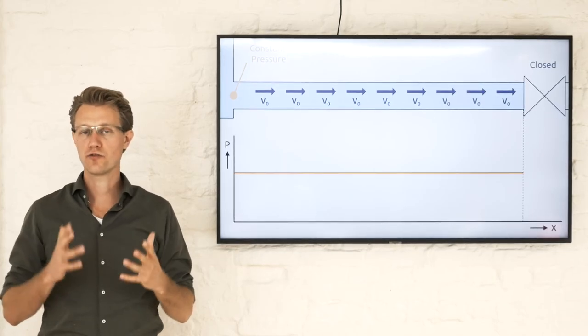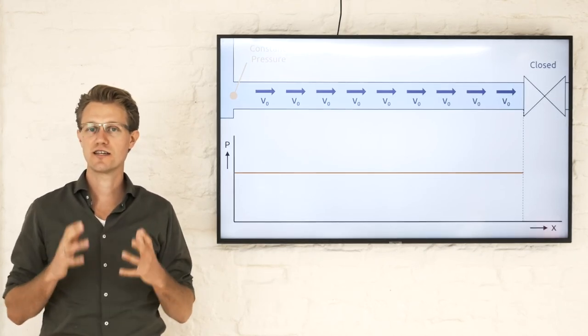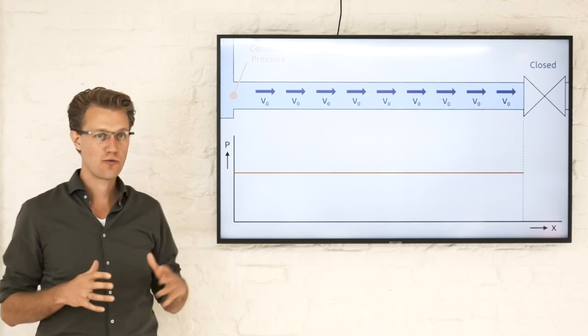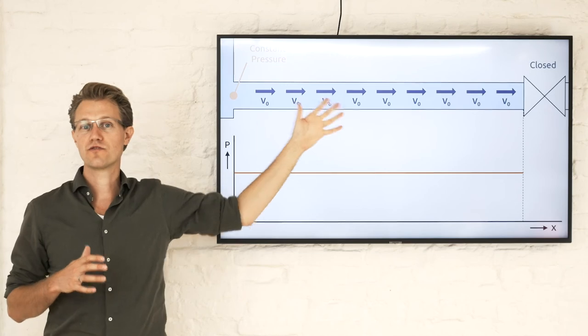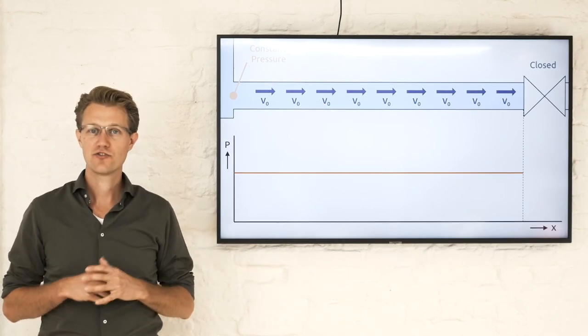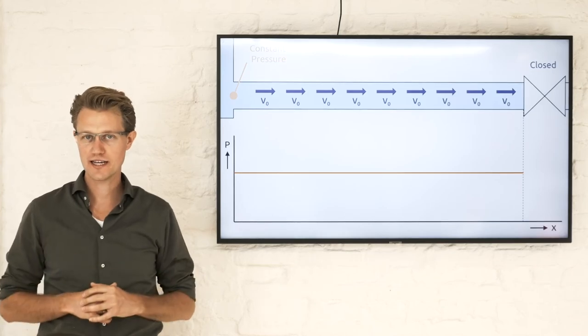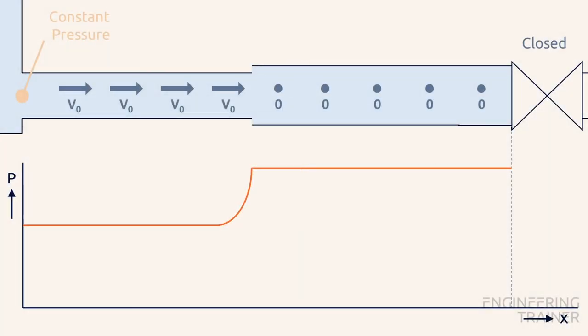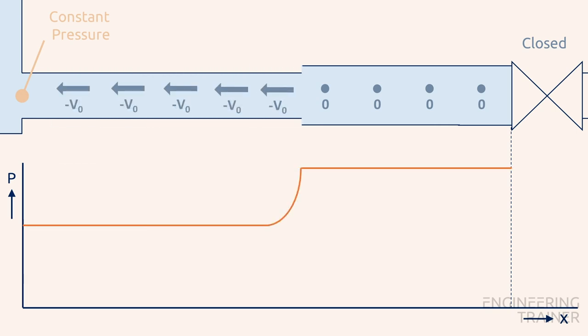Now that the front of the pressure wave is back at the valve, the situation we've reached is exactly similar as our starting point. We have water running from the reservoir to the closed valve with velocity V0. The complete loop of pressure waves now simply starts over from the beginning. A pressure increase is created which runs through the pipe and reflects back to zero at the fixed pressure of the reservoir.